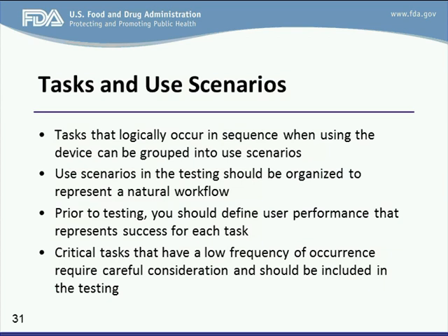And during your preliminary analysis or design development process, if you choose to use your own software testers or your partners in your testing, I think that depends on what kind of results and objective you are trying to achieve for those preliminary studies. As long as it meets your objective and serves the purpose, I think it's a case by case discussion. But again, for the final human factors validation testing, as the guidance says, you should avoid using your own employees and use a minimum of 15 participants per each user group.